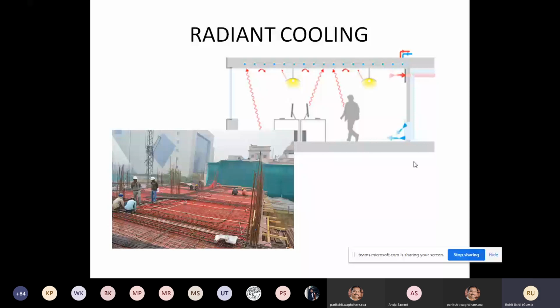What you do is, you can see these are the red pipes which are laid in a network in the RCC structure, and then concrete is poured onto it, so it gets integrated into the structure. If you can see in the visual image over here, in this section, the little blue dots are the pipes which are embedded in the slab. And what we do is simply we pass not chilled water, we pass cool water, which is at about 15 to 17 degrees Celsius, and it slowly cools the whole building envelope down without having to actually provide the air handling units and all these things. Radiant cooling is a very effective method of energy saving in air conditioned buildings. There's close to 30-35% saving over any conventional kind of air conditioning system.